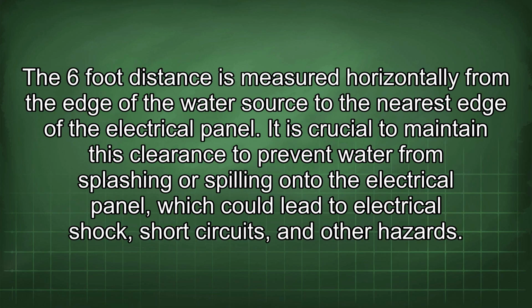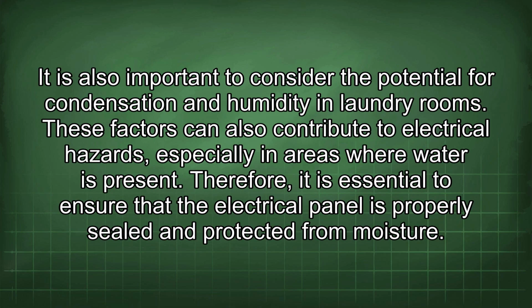The 6-foot distance is measured horizontally from the edge of the water source to the nearest edge of the electrical panel. It is crucial to maintain this clearance to prevent water from splashing or spilling onto the electrical panel, which could lead to electrical shock, short circuits, and other hazards. It is also important to consider the potential for condensation and humidity in laundry rooms. These factors can also contribute to electrical hazards, especially in areas where water is present. Therefore, it is essential to ensure that the electrical panel is properly sealed and protected from moisture.